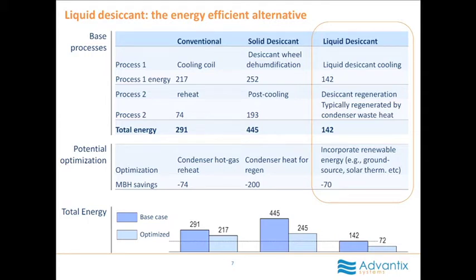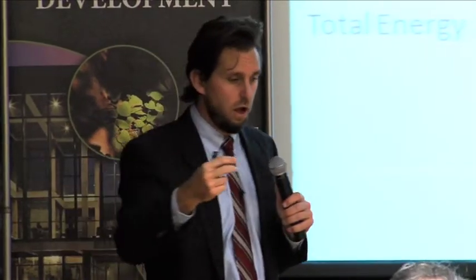Yep. On the liquid desiccant, you need to take air to the dew point temperature. Is something else different? No, you don't, and that's the beauty, it's a chemical attraction. So you're directly extracting, via what on the chemistry level is a polar attraction between the salt molecules in the desiccant and the free-floating water molecules, which are vapor at that time. Another way to say it is that you are actually bringing the dew point down, way down, or you're bringing the vapor pressure down so that you've actually gone beyond the natural dew point of that water vapor, even without bringing it to such a cold temperature.